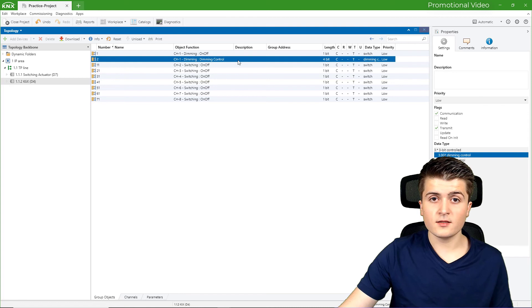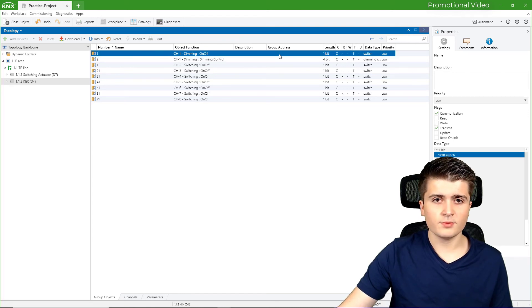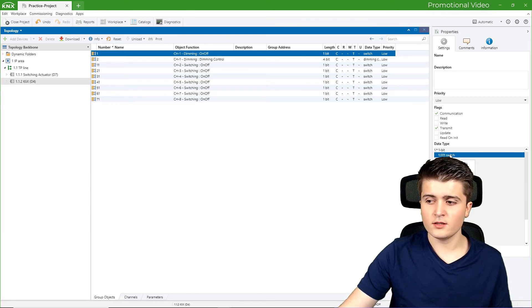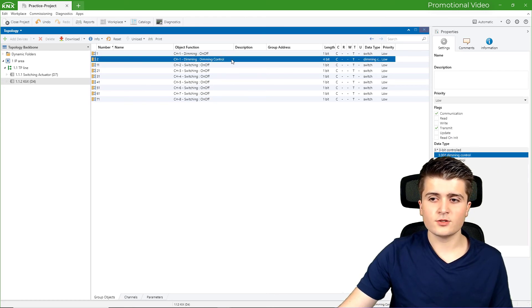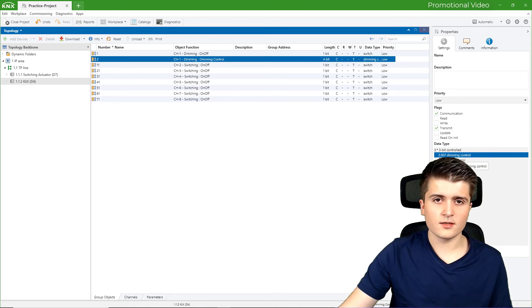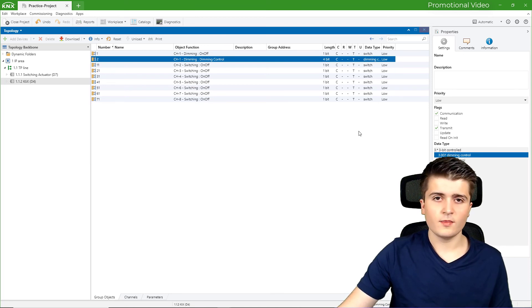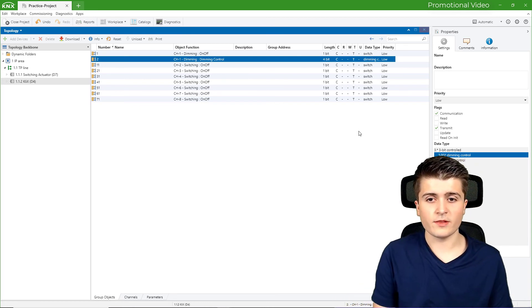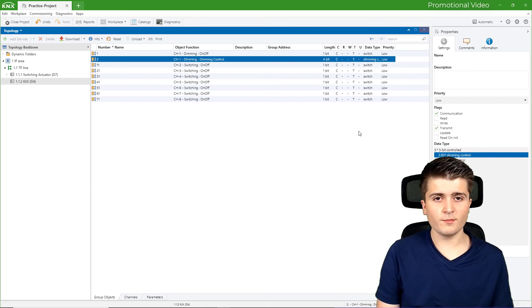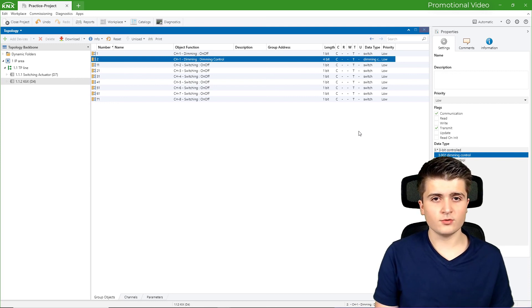Now you can also see the different data types we have. Here we have a length of 1 bit for on and off — you can also see it below: switching, where value 0 means off and value 1 means on. And if I go down to dimming control, we can see a length of 4 bits. Dimming control is the data type, and there we now have additional values like dimming up, dimming down, etc. So there we get the information of the push button sensor as a group object.